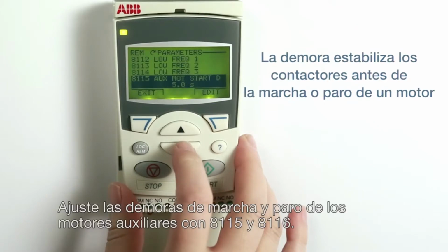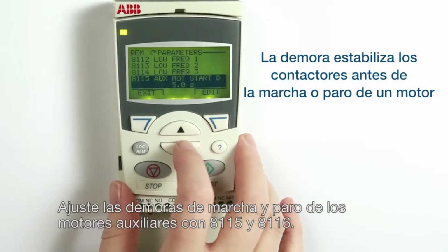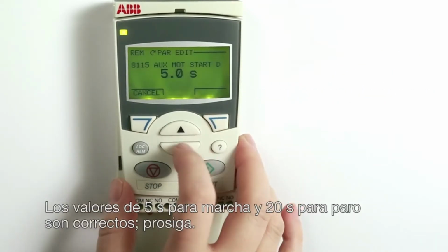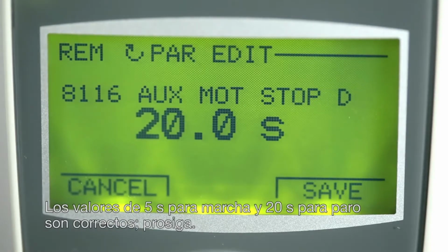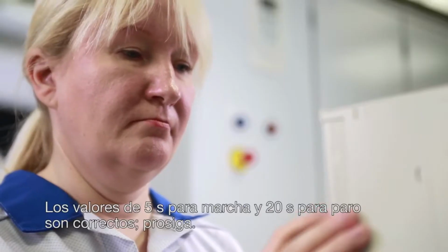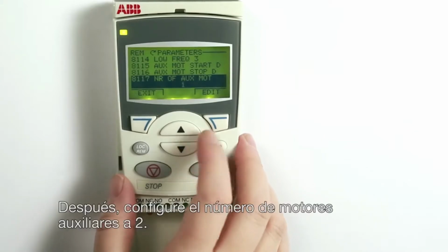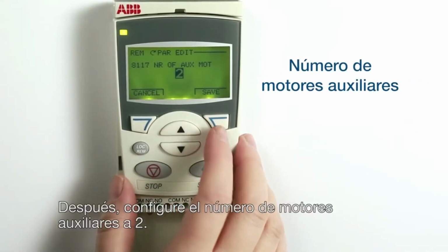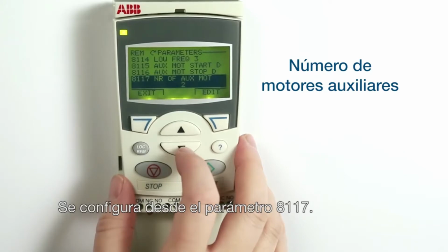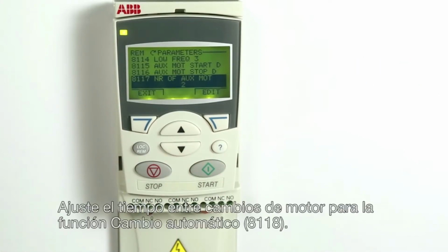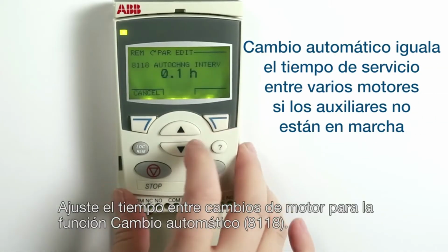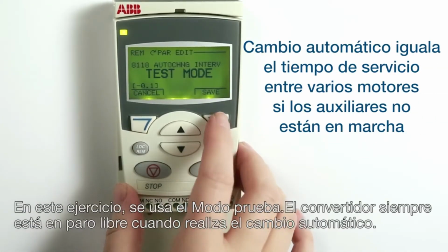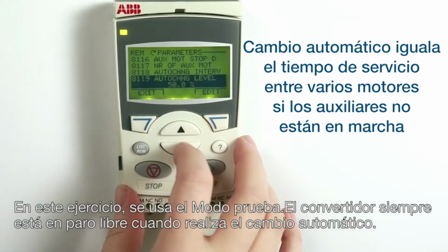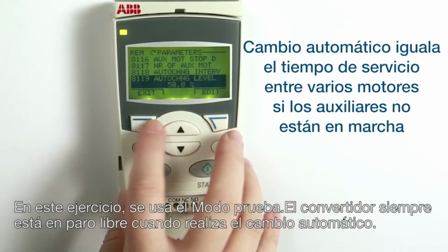Then we set the auxiliary motors' start and stop delays by setting parameters 8115 and 8116. The default values, 5 seconds for start and 20 seconds for stopping, are OK, so we continue to the next parameter. Next we set the number of auxiliary motors to 2. This is set from parameter 8117. Then we set the interval between motor changes for the auto change function, parameter 8118. In this exercise we use test mode. The drive always coasts to stop when auto change is performed.